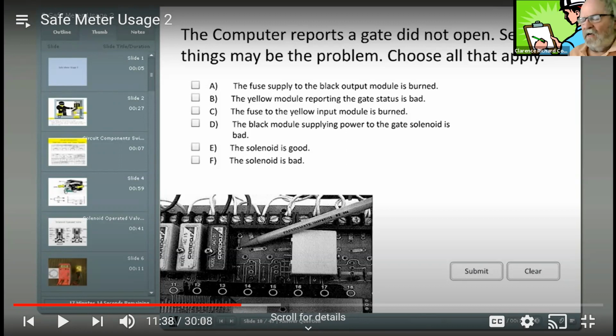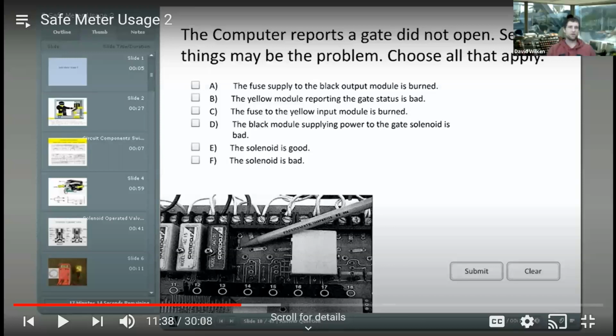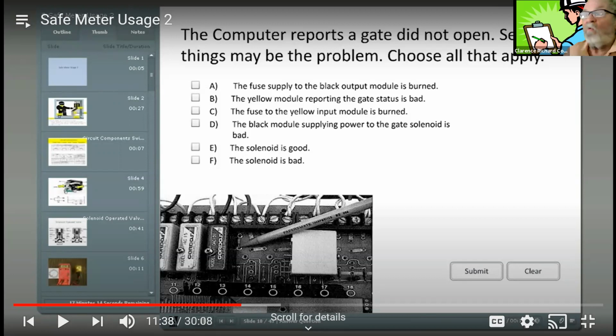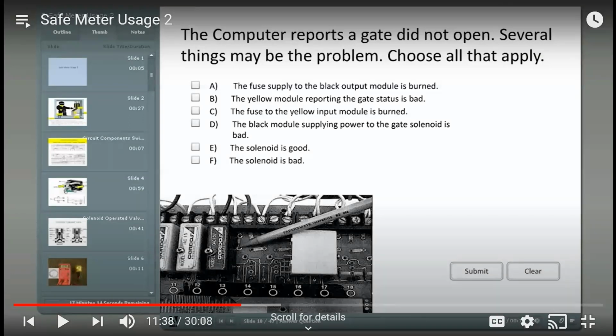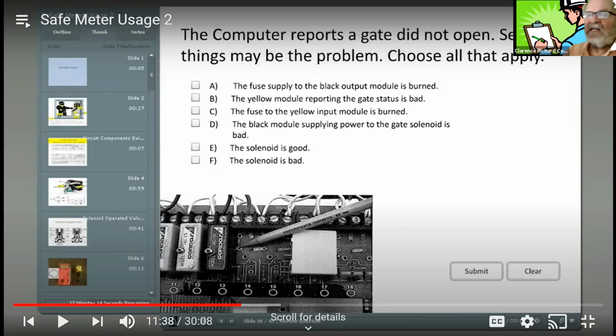The module telling it to open up, and then if it did open up, then come back, and did that report it? So we're looking at a report. All those are true so far. Great. How about the solenoid? Is the solenoid good or bad? Do we know? Could it be bad? Well, it could be. And it could be good too as well, couldn't it? You skipped over D there, Clarence. The black module supplying the gate solenoid is bad. Would that cause it? Yeah. And the fact that it didn't report bad doesn't mean either way if the solenoid is good or bad. Is that correct? Correct. So the solenoid could be good and the solenoid could be bad. So in my way of thinking, I think all of those.